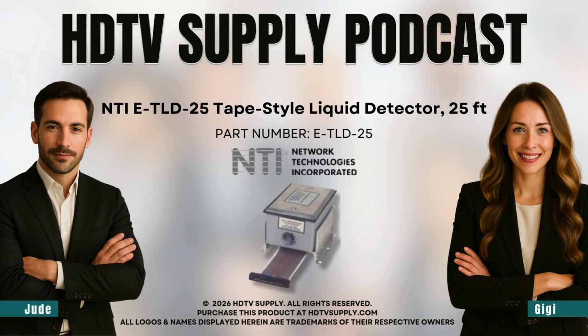Okay, that makes sense. But what about the tape itself? You've got 25 feet of this sensor running under equipment, maybe in a hard-to-reach place. How do you know the whole thing is still working? That's the critical feature, the peace of mind part. The system runs a continuous tape integrity self-check. It's constantly monitoring itself, so if someone accidentally cuts the tape or it gets damaged, it doesn't just fail silently. It alerts you immediately that the monitoring system itself has a problem. It's a diagnosis before the disaster.